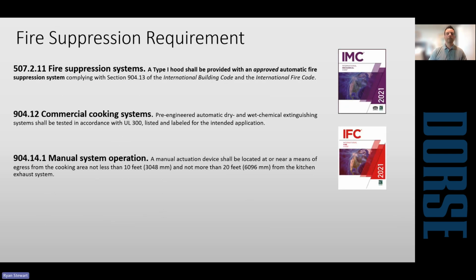So type 1 hoods, the code says that they require fire suppression. It needs to be an automatic fire suppression system. And then they reference chapter 9 of the code book, which basically says it needs to be a pre-engineered automatic dry or wet chemical system tested in accordance with UL 300. I'm not aware of any dry chemical systems associated with hoods. Pretty much everything's wet chemical or even some sprinkler-based systems.